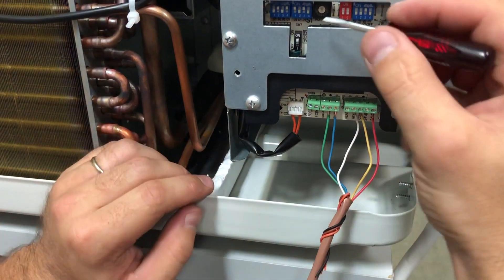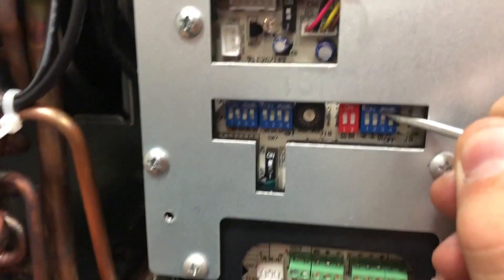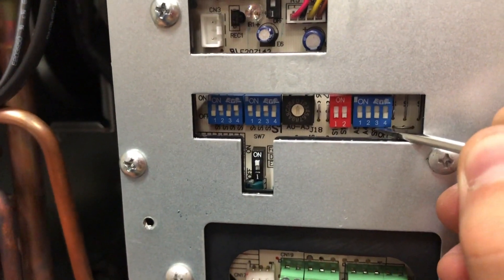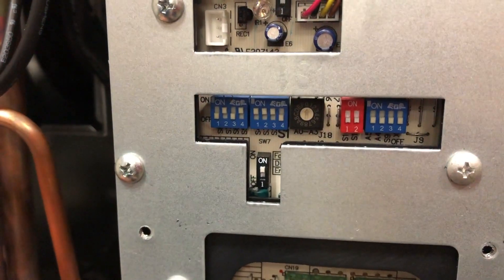Now that the wall thermostat is connected, it needs to be activated. Switch S1 and switch S9 to the off position, and switch S3 to the on position. Now your wall thermostat is ready for use.